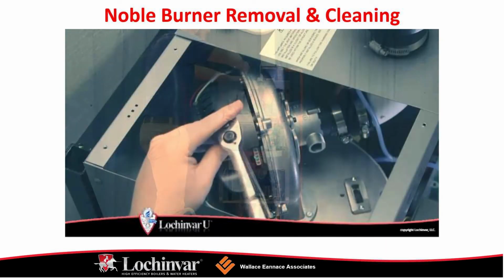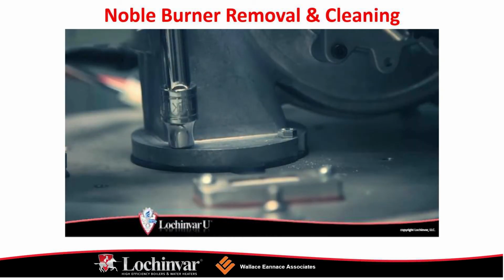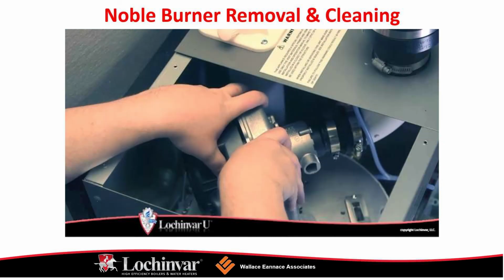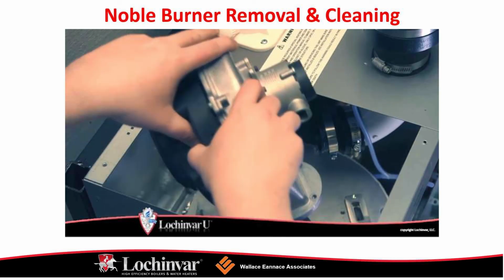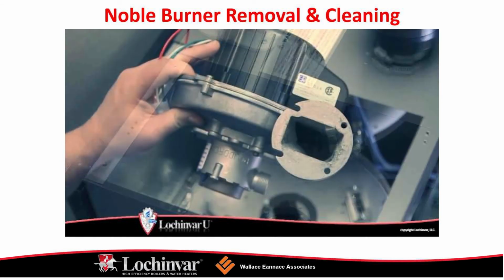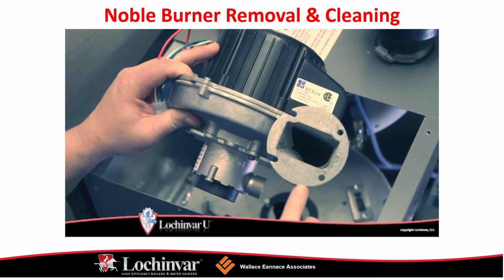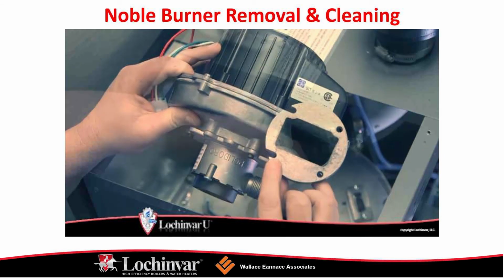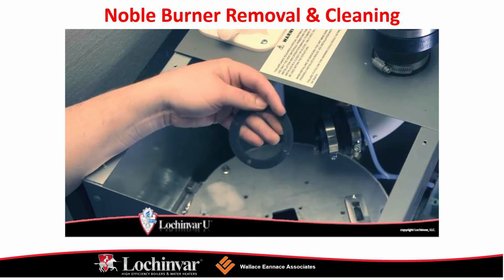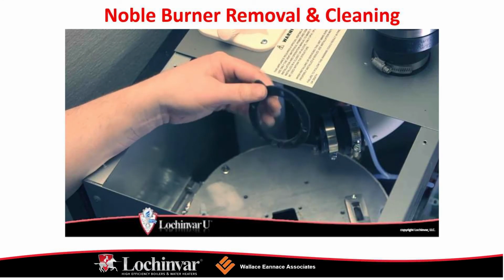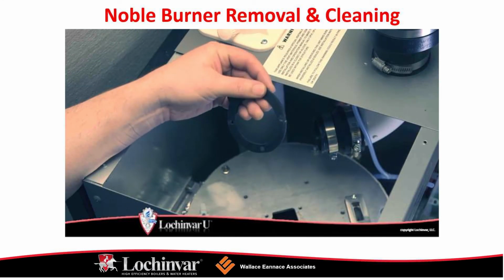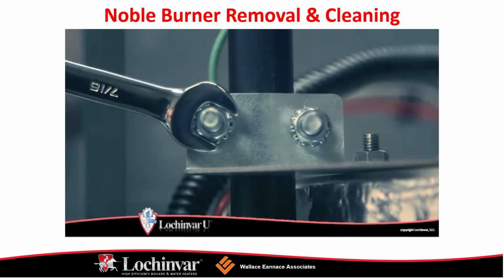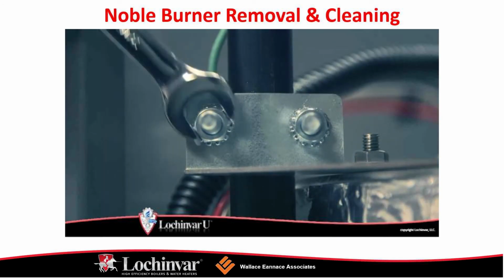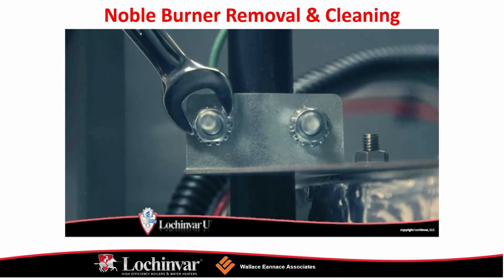Burner removal and cleaning. Turn off the main power. Then turn off the main gas supply to the unit at the external main manual gas valve. If the unit has been in operation, allow the unit to cool to room temperature before proceeding. Then remove the front access panel. Using a Phillips head screwdriver, remove the screw securing the top left access panel to the unit and remove it. Then locate and disconnect the gas valve wiring harness and reference hose from the gas valve.